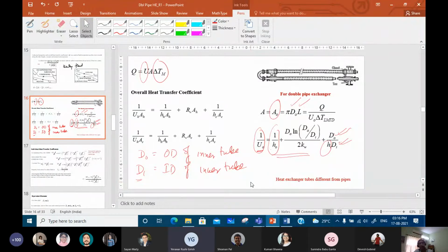It will be higher. When the velocity increases, then what happens to the pressure drop? Can you tell me? It will be higher. So therefore, while you are gaining on the cost of the tubes, you are losing on the utility part, isn't it? You will be requiring a larger pump, greater pumping power, etc., etc.